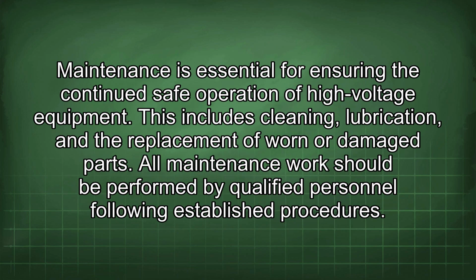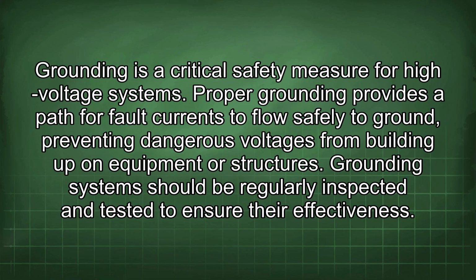Maintenance is essential for ensuring the continued safe operation of high-voltage equipment. This includes cleaning, lubrication, and the replacement of worn or damaged parts. All maintenance work should be performed by qualified personnel following established procedures. Grounding is a critical safety measure for high-voltage systems. Proper grounding provides a path for fault currents to flow safely to ground, preventing dangerous voltages from building up on equipment or structures. Grounding systems should be regularly inspected and tested to ensure their effectiveness.